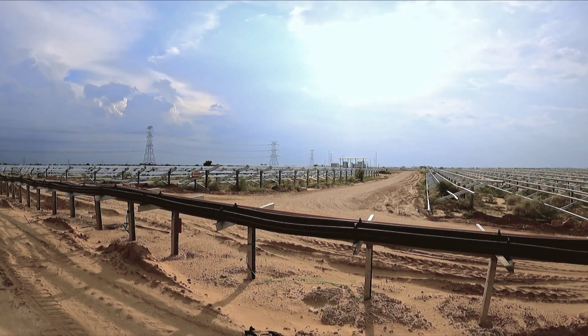With the sun from above creating a temperature of more than 47 degrees Celsius and burning sand underneath, laying of cable in such a vast area was the major challenge. The cables are not trouble-free. The capacity of the cable or the increase in the size of cable in such a large network is also a problem because it creates an ill effect which is called reactive power, and managing that reactive power in such a huge cabling network was an art of engineering.